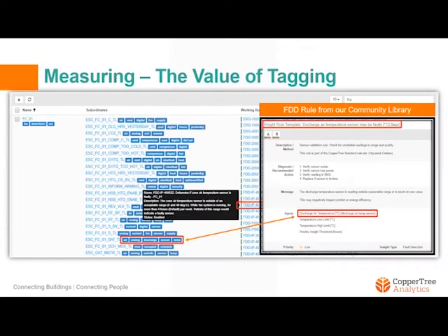This example is showing the tags associated with a discharge air temperature sensor and how our rules are set up to identify these tags. We can see the text shown in light blue for our SAT, or supply air temperature sensor. To the right of that, within the blue boxes, you'll see the tags that have been applied to this sensor, which include air, analog, discharge, sensor, and temp. The function of this particular rule is to identify if a discharge air temperature sensor may be faulty, and therefore a rule will be applied to all discharge air temperature sensors within the building that include these tags. There are, of course, other benefits to tagging, but we'll leave it at this for now.